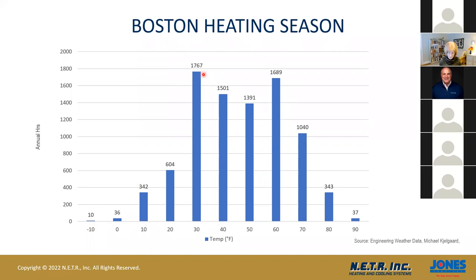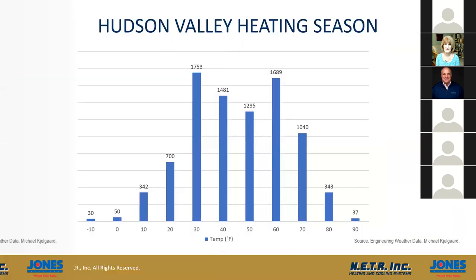And this is where air source heat pumps are super, super efficient, within these temperature ranges right here. When you start looking at these two temperature ranges, again, when you look at 60 degrees, 70 degrees, and you look at the air conditioning hours, we really didn't have a lot of hours over 90 degrees last year. So that's the Boston area, but I want you to keep these hours in mind because you're going to use those in a second, okay?